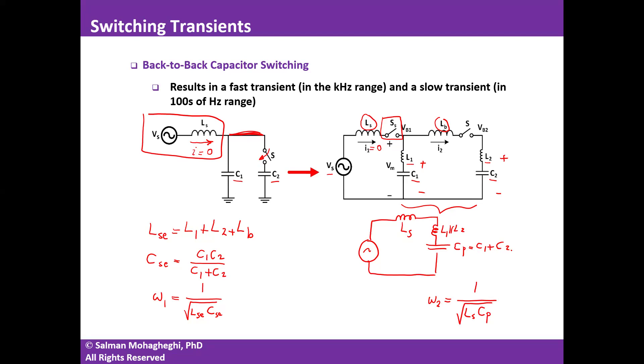Back-to-back capacitor switching consists of two transients: a faster transient at frequency ω₁, typically in the range of a few kilohertz, and a slower transient at frequency ω₂ in the range of tens to hundreds of hertz. In a system voltage waveform, you will see a high-frequency oscillation followed by a lower-frequency oscillation. When you observe two oscillations that follow one another — one high frequency, one low — that is typically indicative of back-to-back capacitor switching.